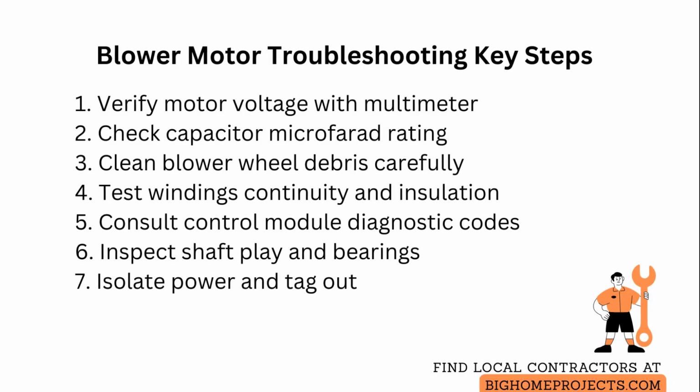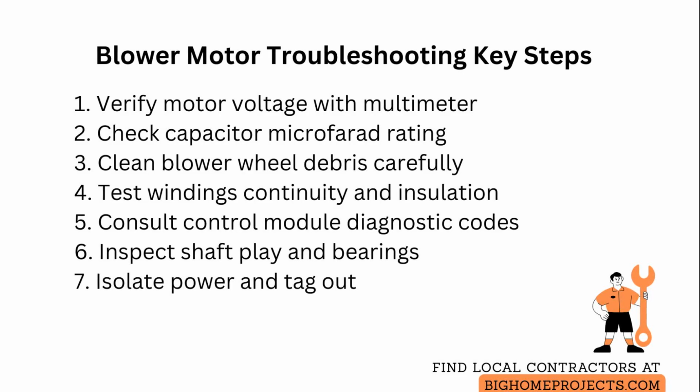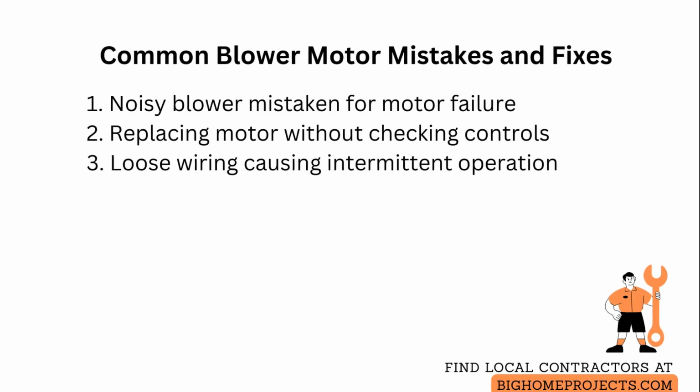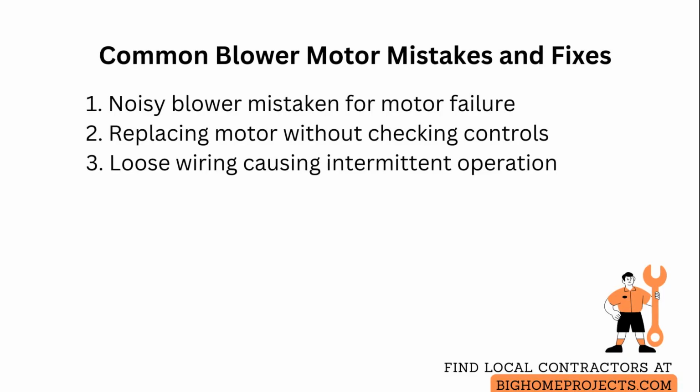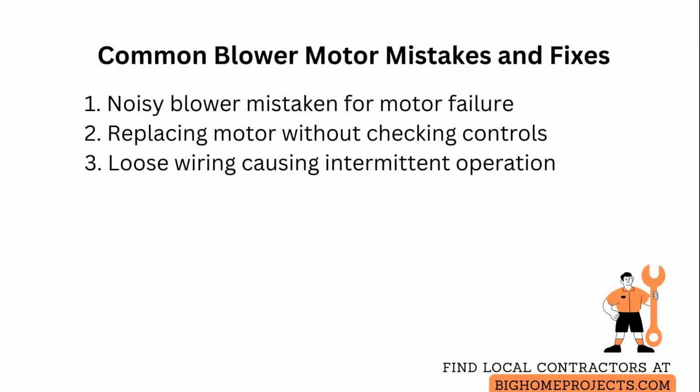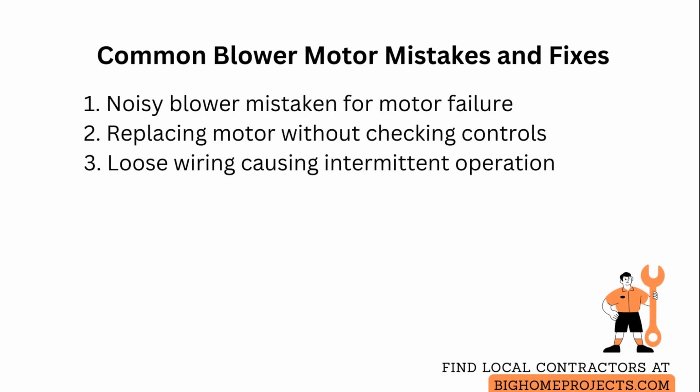Use basic safety practices: isolate all power, tag out the system, discharge capacitors before handling, and wear eye protection and gloves. Three common mistakes are assuming a noisy blower equals motor failure when often the wheel is imbalanced or rubbing. Spin and inspect the wheel first and true it, or replace it if needed.